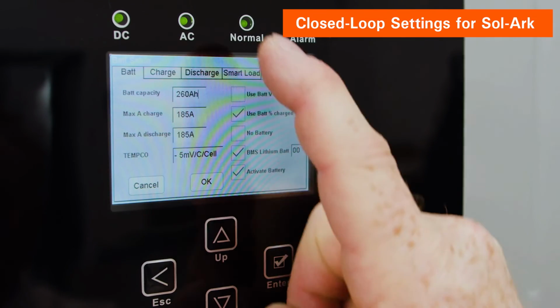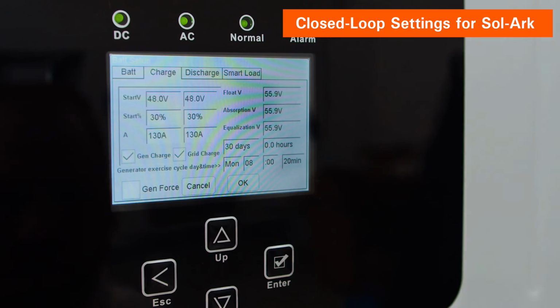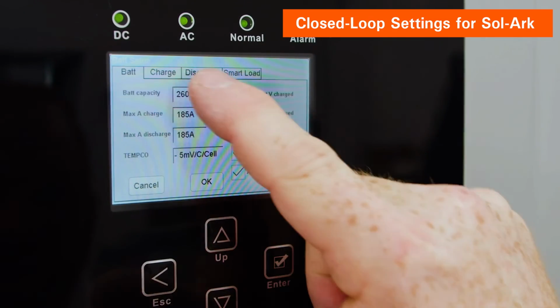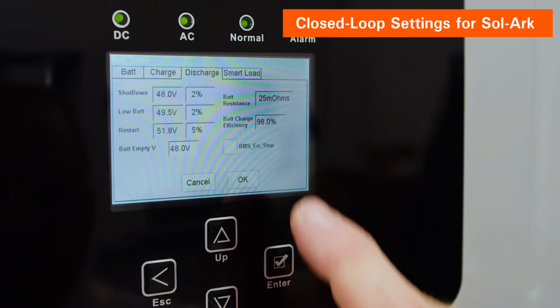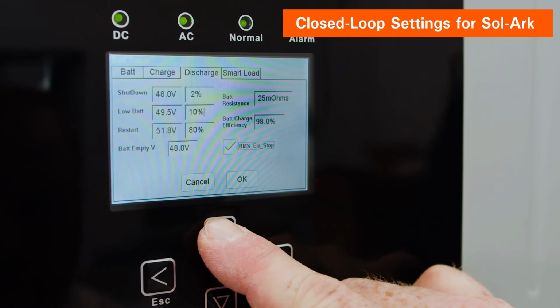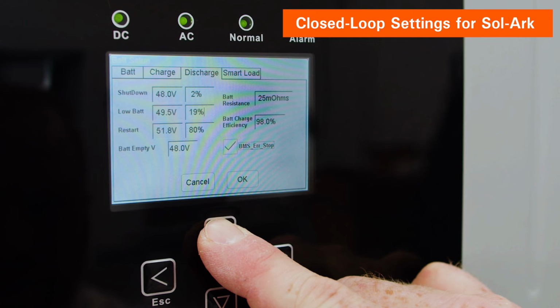Next, on the charge screen, set the start percentage parameter and the amp values, which should be the same as the max charge amp values. On the discharge screen, ensure the BMS error stop function is enabled and set the other percentage-based triggers.